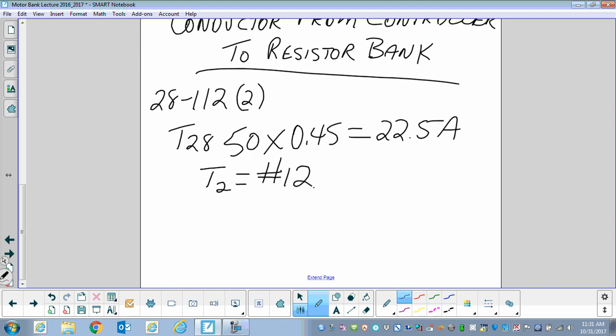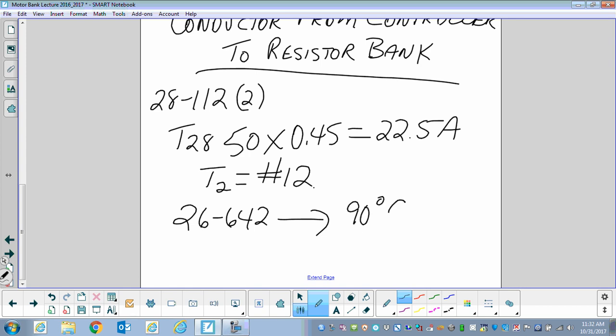But there's one more consideration: we're hooking up to a resistor bank, so the insulation rating matters. Rule 26-642 talks about resistive devices, and it tells us that when we buy this wire, the number 12 must have a minimum insulation rating of 90 degrees Celsius. Those resistors heat up, and that heat conducts into the wire, so we need a conductor that can effectively dissipate heat.